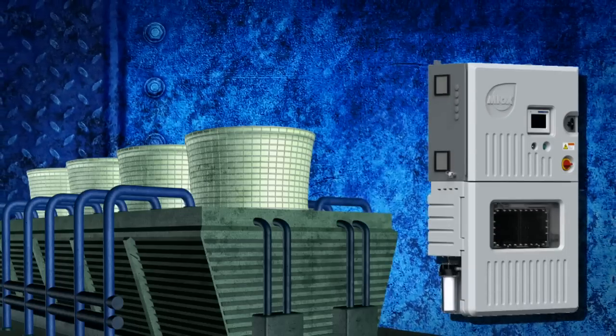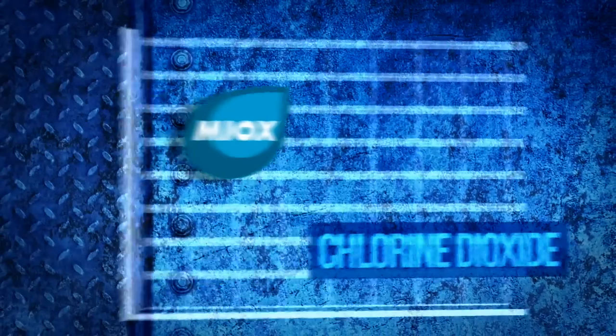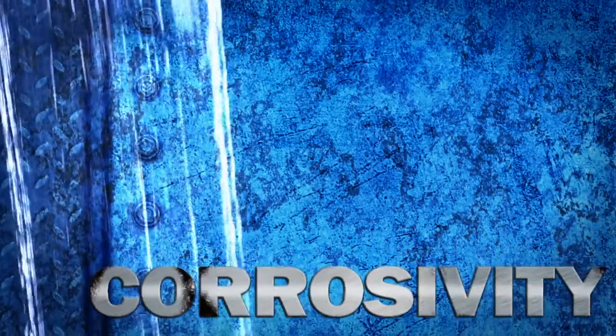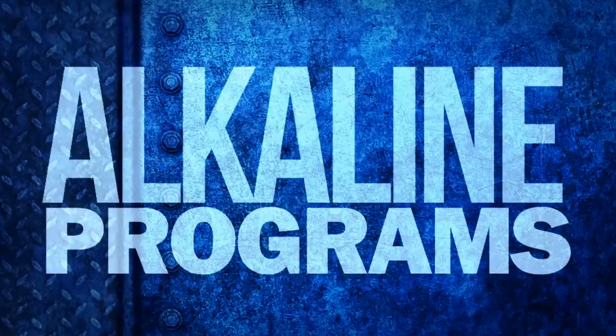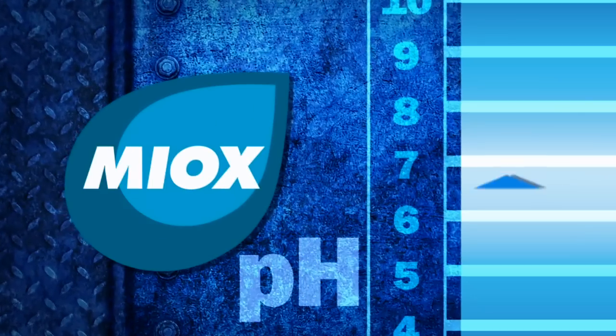Here's how it works in your tower. MIOX replaces all biocides used in your water systems. MIOX offers a combination of bleach and peroxide, which is as effective as chlorine dioxide. The peroxide creates fissures in the biofilm, allowing the hypochlorite to kill underneath the slime layer. This reduces chemical dosing and lowers the ORP, in turn lowering the corrosivity of water and allowing inhibitors to be more effective. And for alkaline programs where bromine is used, MIOX is effective at elevated pHs.